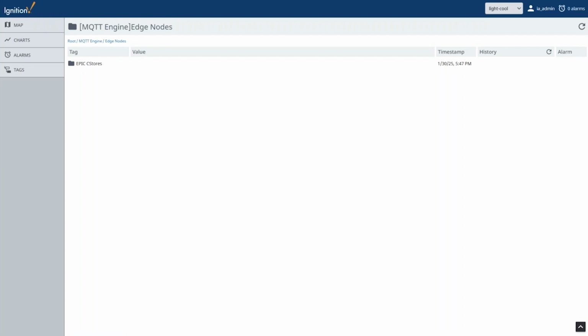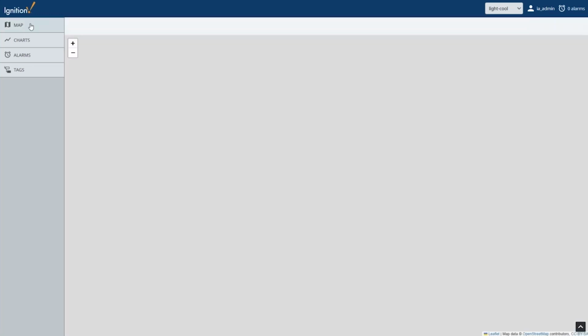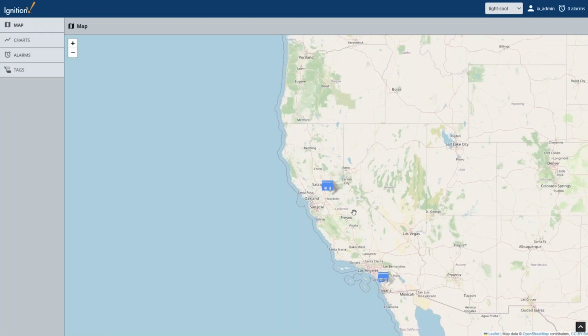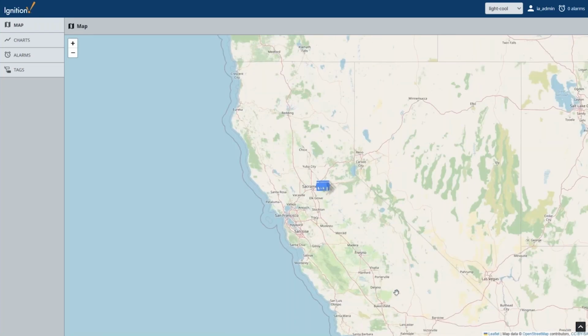Sure. So yeah, it's a good question. And MQTT is like OPC in that it is a communication protocol to move data between two endpoints. The big difference is if you have an OPC UA server, say in a PLC, then you may use an OPC client to pull that data in. The inverse is true for MQTT. Really what you have is on a device, let's say the Epic, it does support native MQTT, so it'll publish its data to a broker. So you can actually use them both simultaneously. And they work very well together.